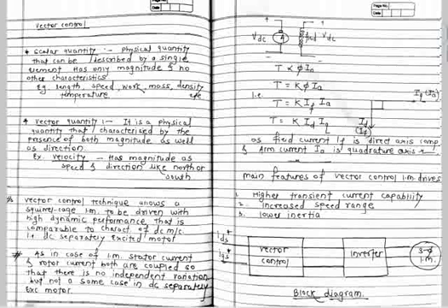So we can use another alternative word. Thus in a scalar control, both torque and the speed are functions of voltage or the current and the frequency, which are mostly interdependent on each other, giving a very sluggish operation of a drive. It means that there is a dependent behavior between the flux and the torque. As you try to control the speed, the torque will get automatically changed, and if you wish to control the torque, the speed will get automatically changed.